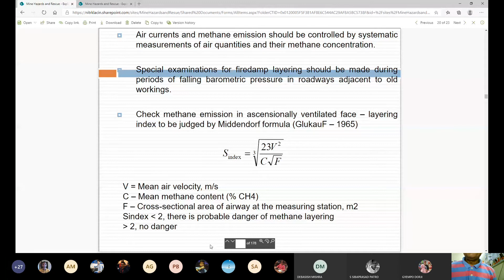The S index, your methane gas layering index, is the cube root of 23 v square divided by c root over f, where v is the mean air velocity in meter per second, c is the mean methane content percentage, and f is the cross-sectional area of the airway at the measuring station in meter square. If your S index is less than 2, there is probable danger of methane layering. If S index is greater than 2, no danger of methane layering. So this formula can be used.